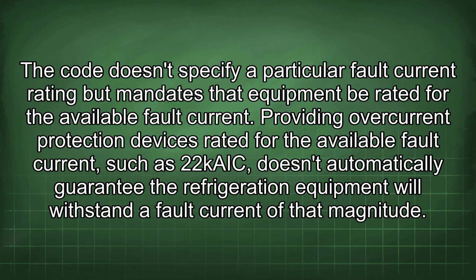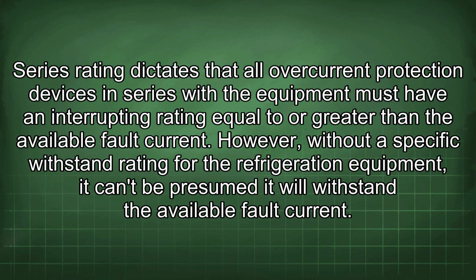current. Providing overcurrent protection devices rated for the available fault current, such as 22kAIC, doesn't automatically guarantee the refrigeration equipment will withstand a fault current of that magnitude. Series rating dictates that all overcurrent protection devices in series with the equipment must have an interrupting rating equal to or greater than the available fault current.